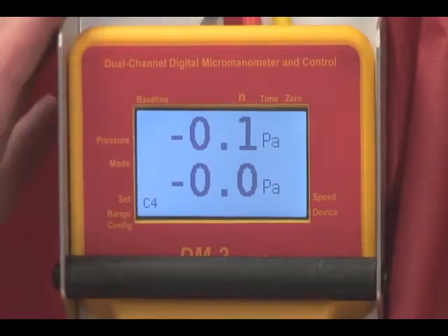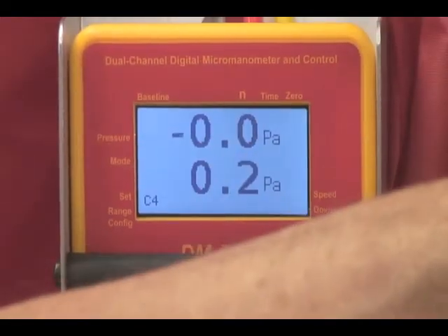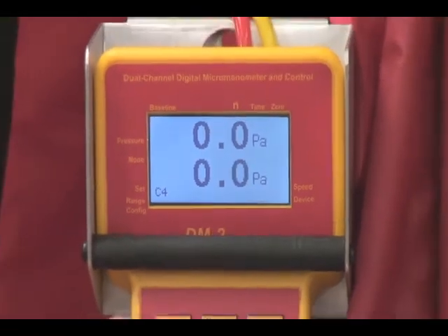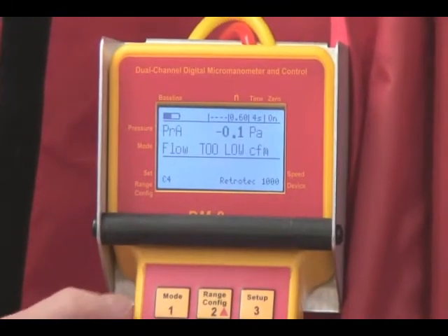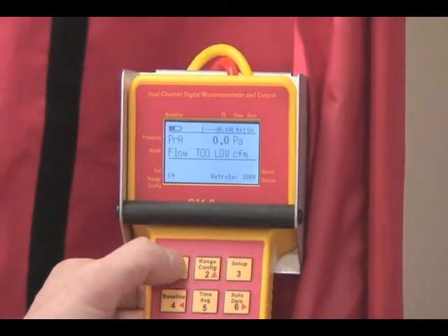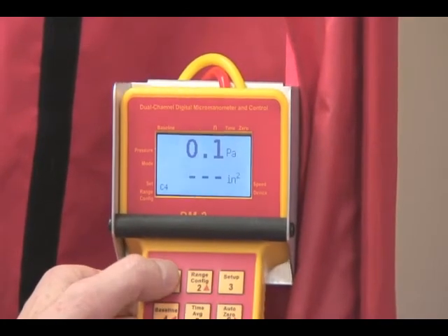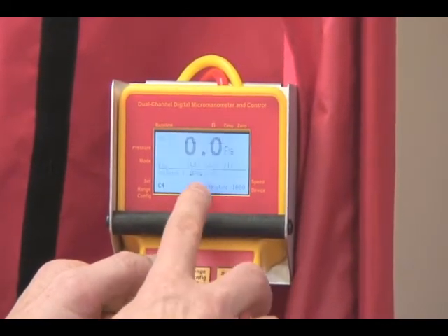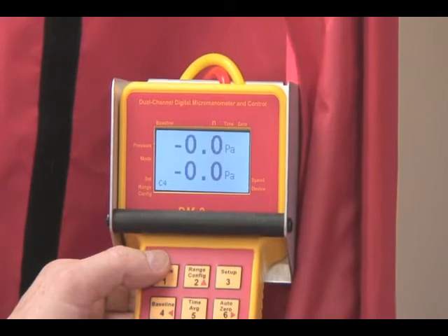We're going to show the same units on this gauge, which performs in a very similar way, but slightly different in mode. We've also made changes in the setup menu to duplicate what we have over here as exactly as possible. So when we hit the mode key, and I'm just going to hold the exit down here temporarily, we've got pressure, CFM, pressure, EQLA in square inches, and air changes per hour, and then back to pressure.